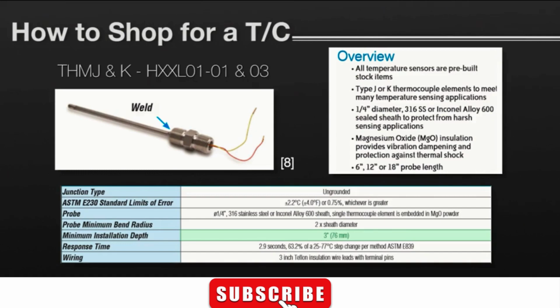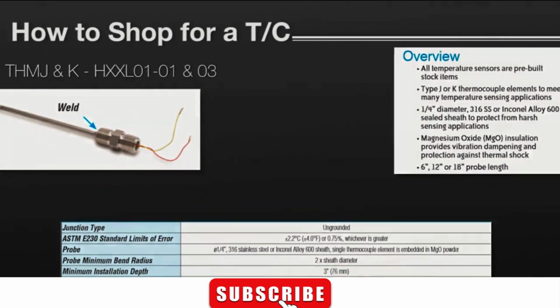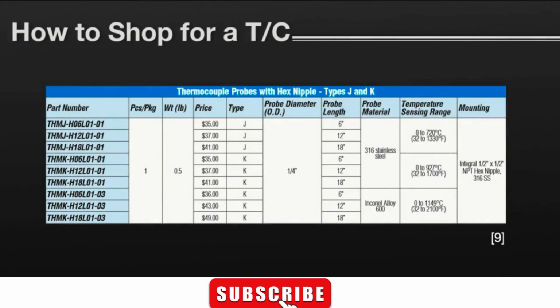This means that you must have the probe inserted at least 3 inches, or the 76 millimeters, into the furnace or oven in order to get an accurate reading. Otherwise, the thermal mass of the probe outside of the furnace will be enough to conduct away the internal heat within the probe tip, which gives you an incorrectly low reading. You select a part number to order based on the mechanical specs you need. The probe comes in 3 standard lengths.